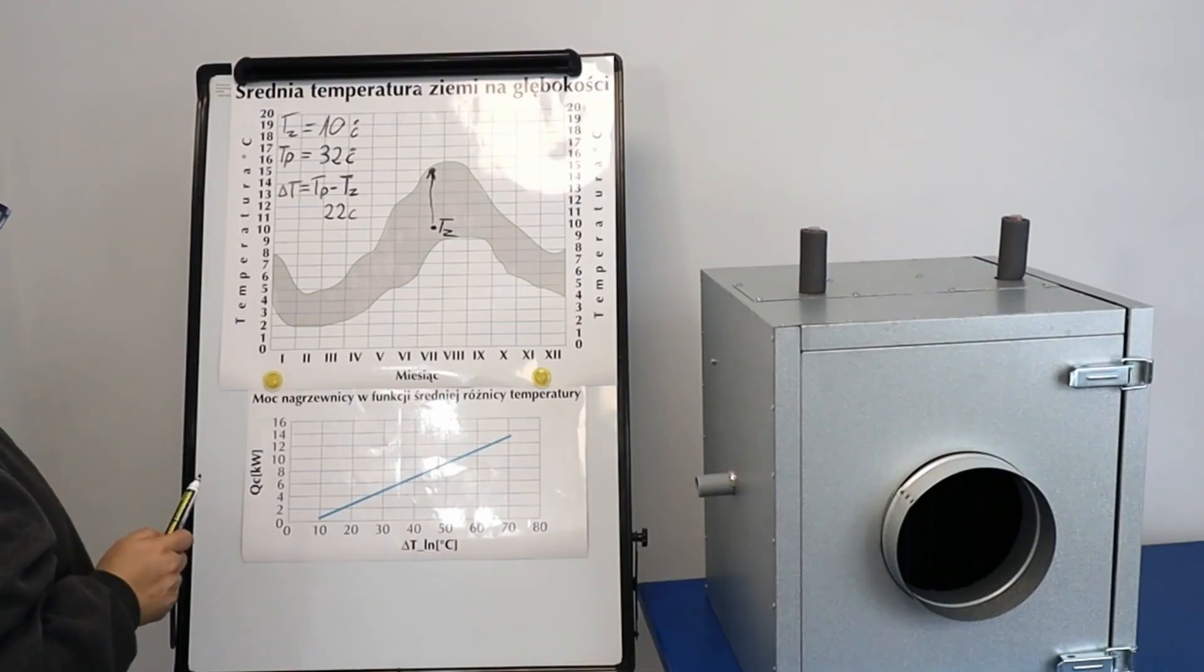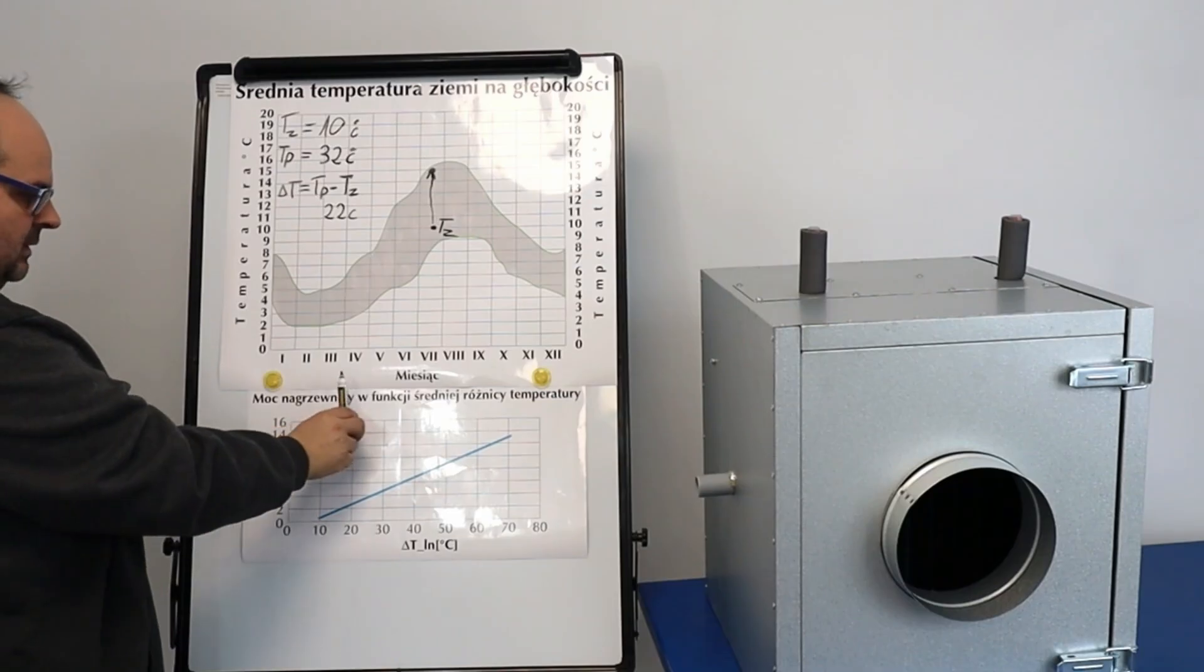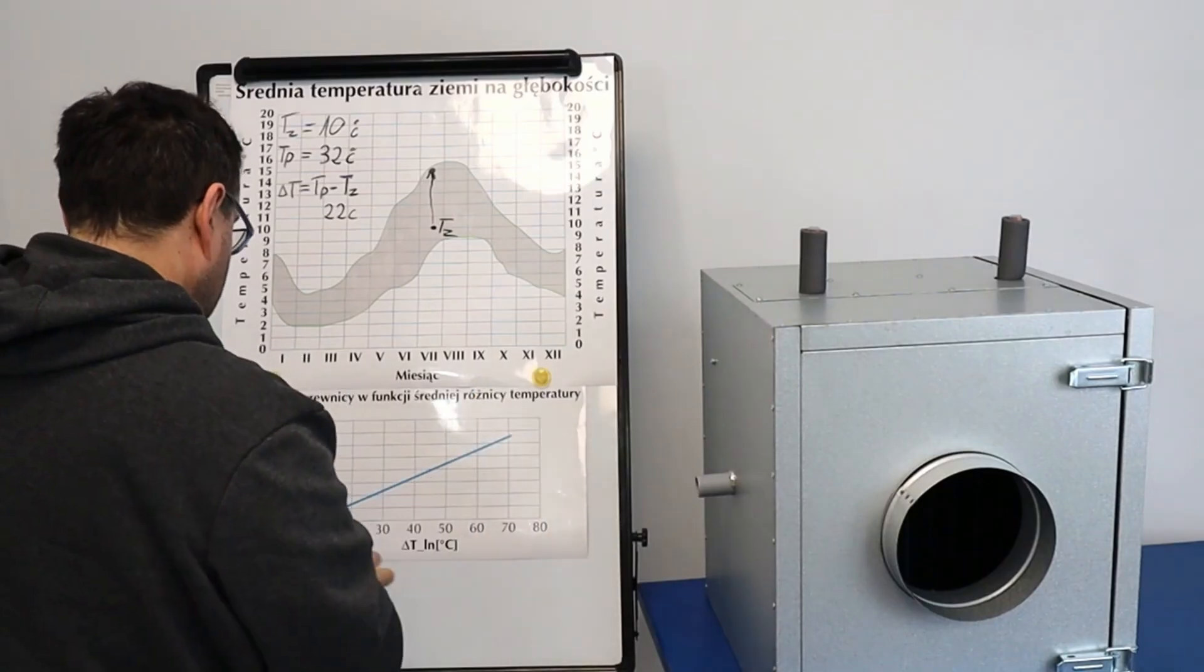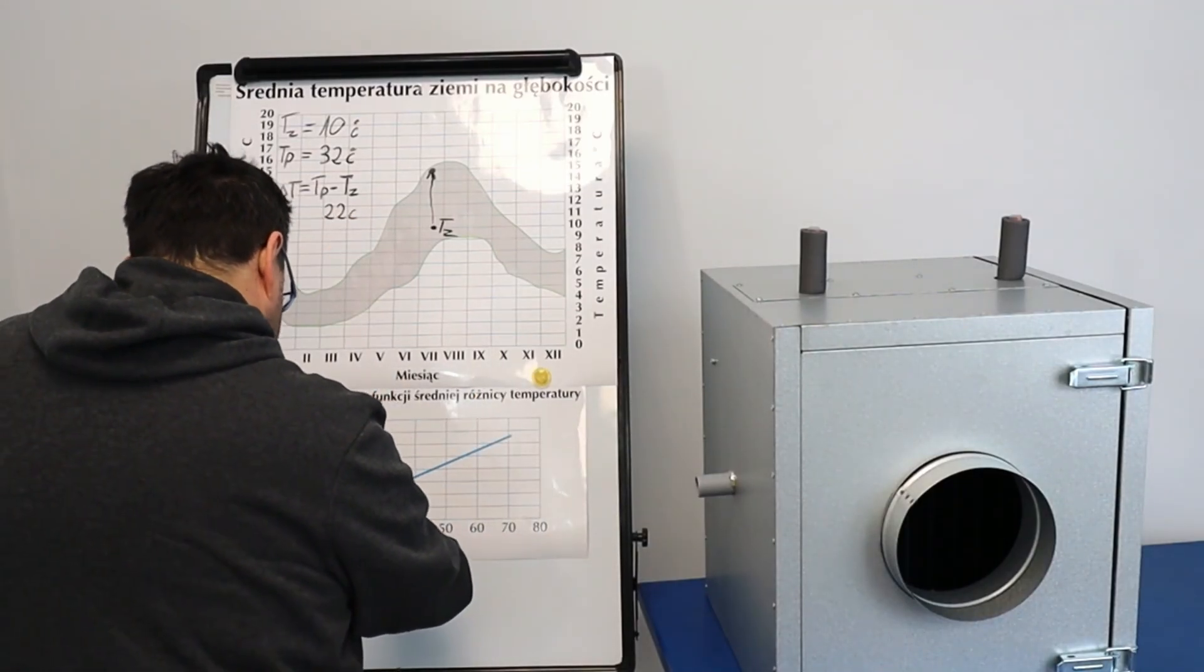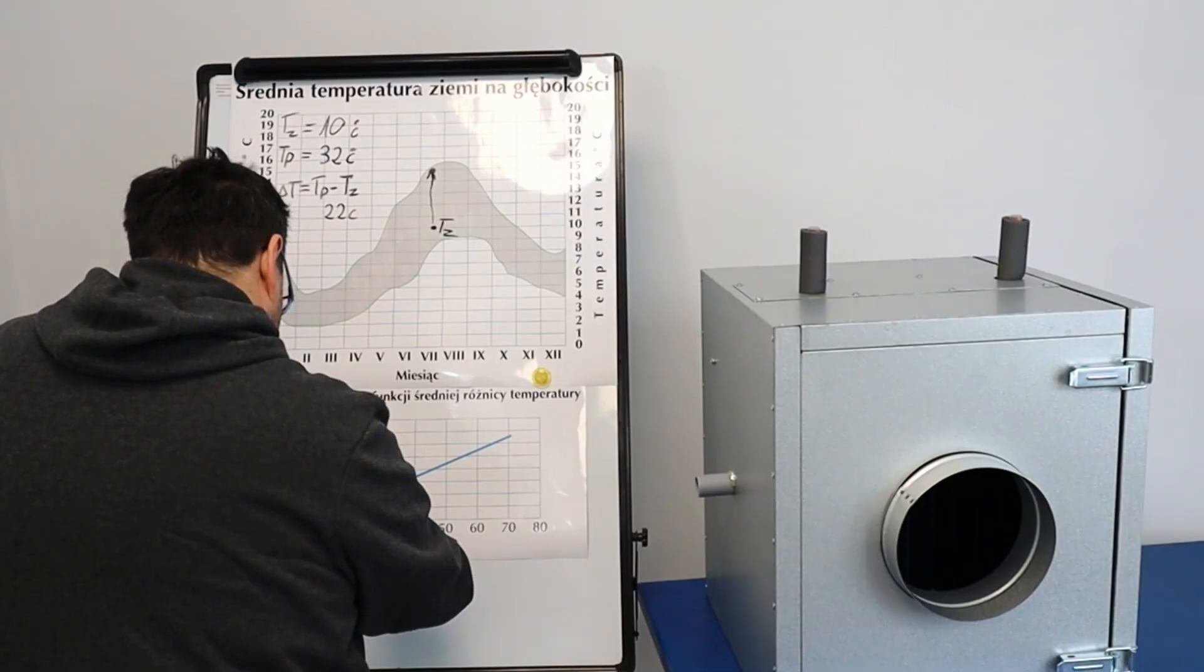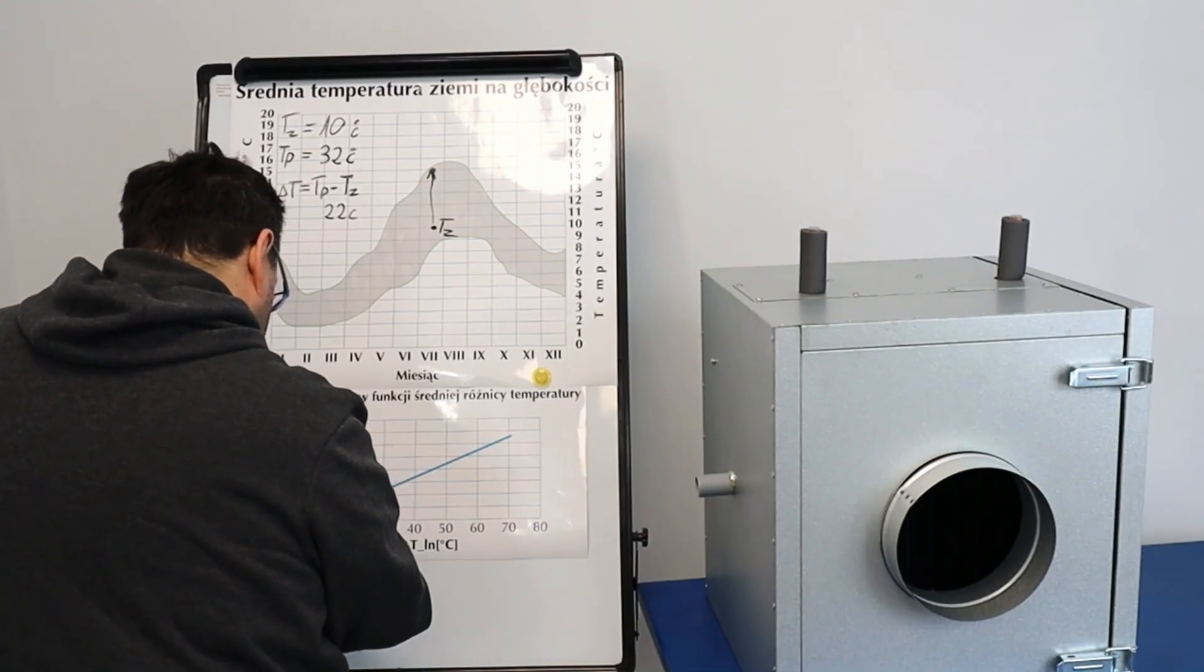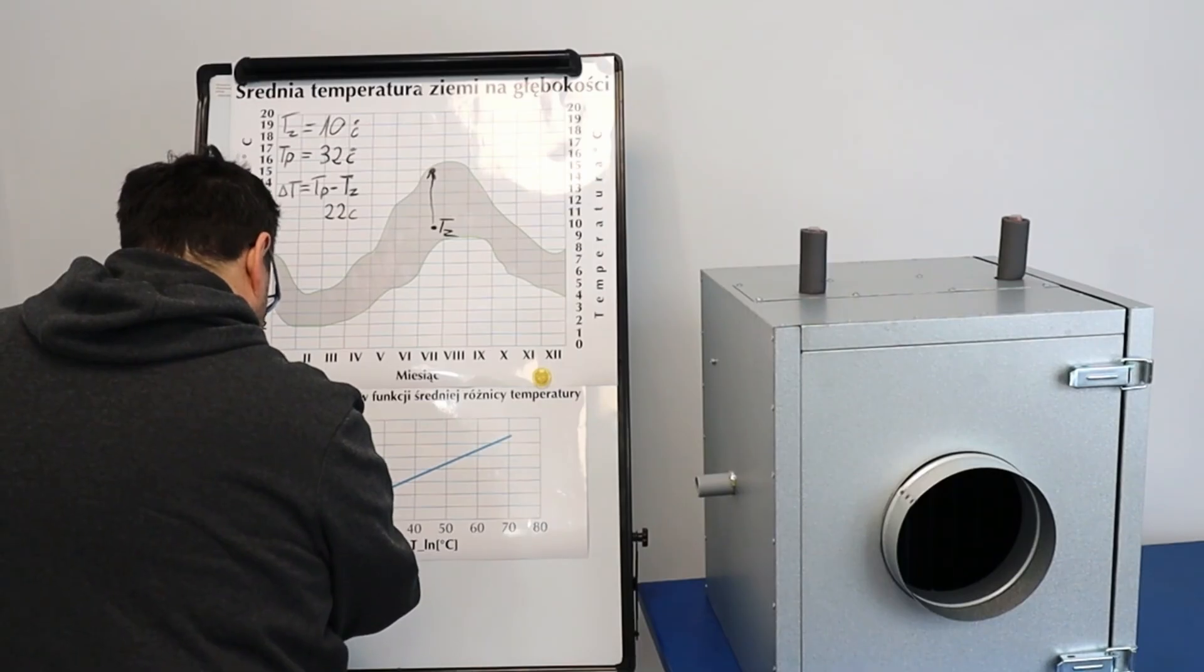So now look. We go to our chart. This is heater power as a function of the average temperature difference. This is the power of this device. And it's 22 degrees. We have 22 degrees here. We're moving. And here you have power somewhere around 3 kilowatts.